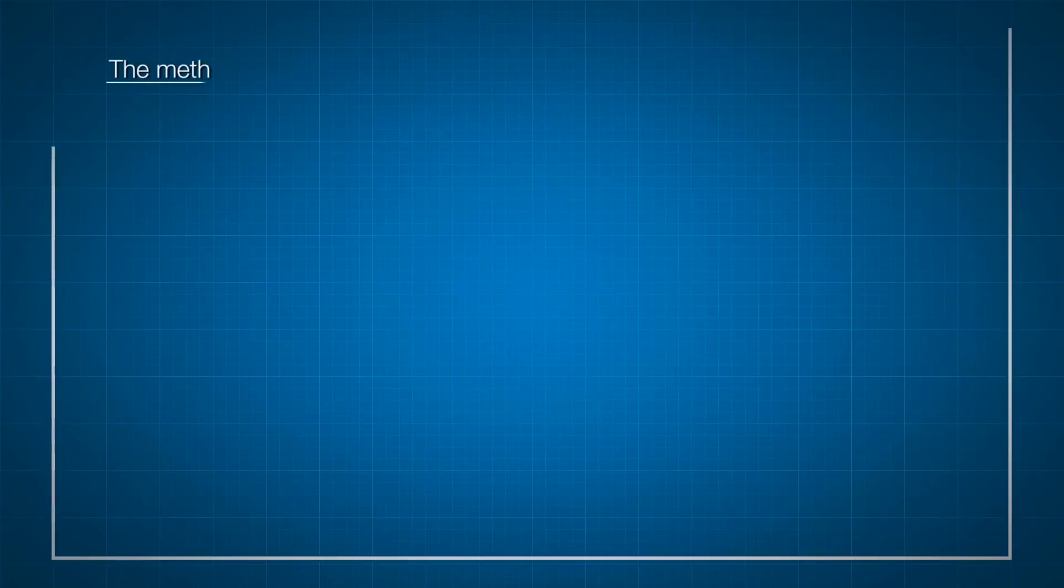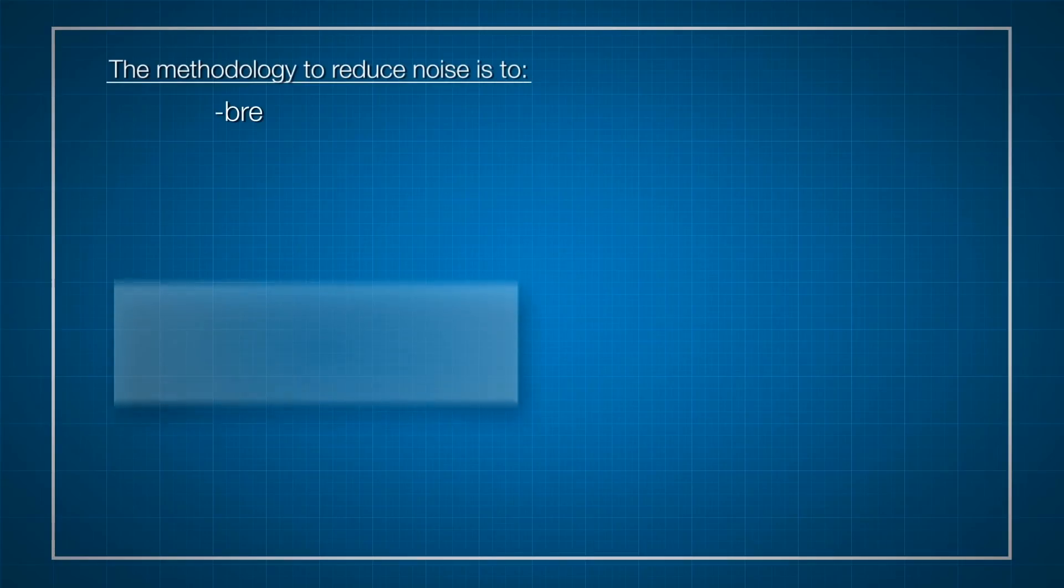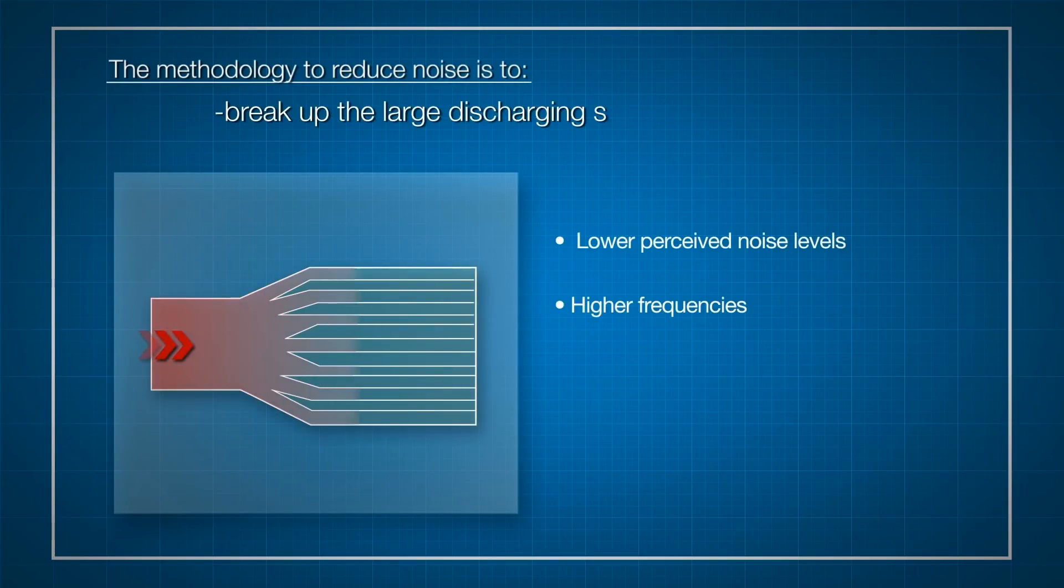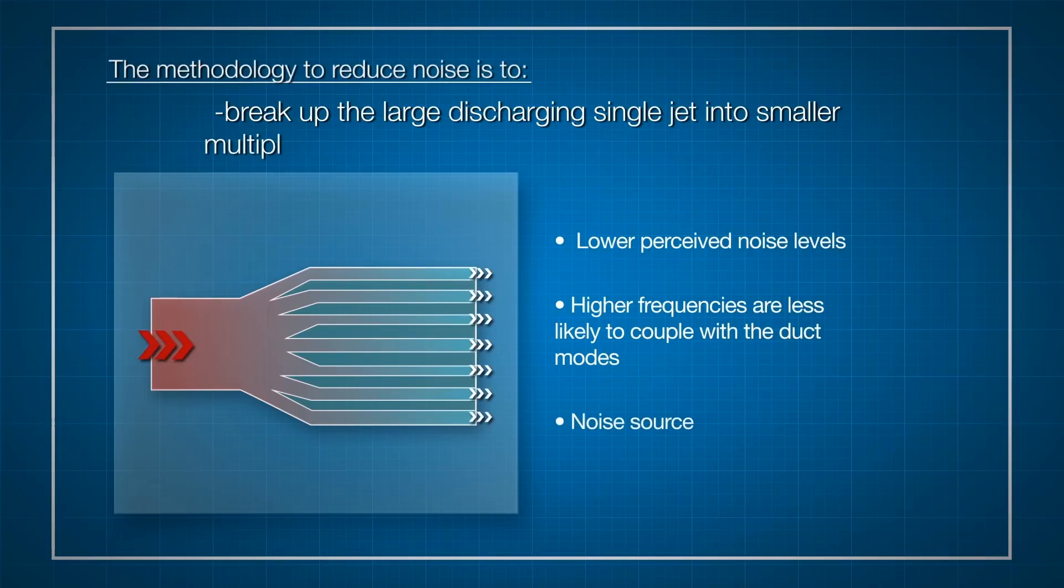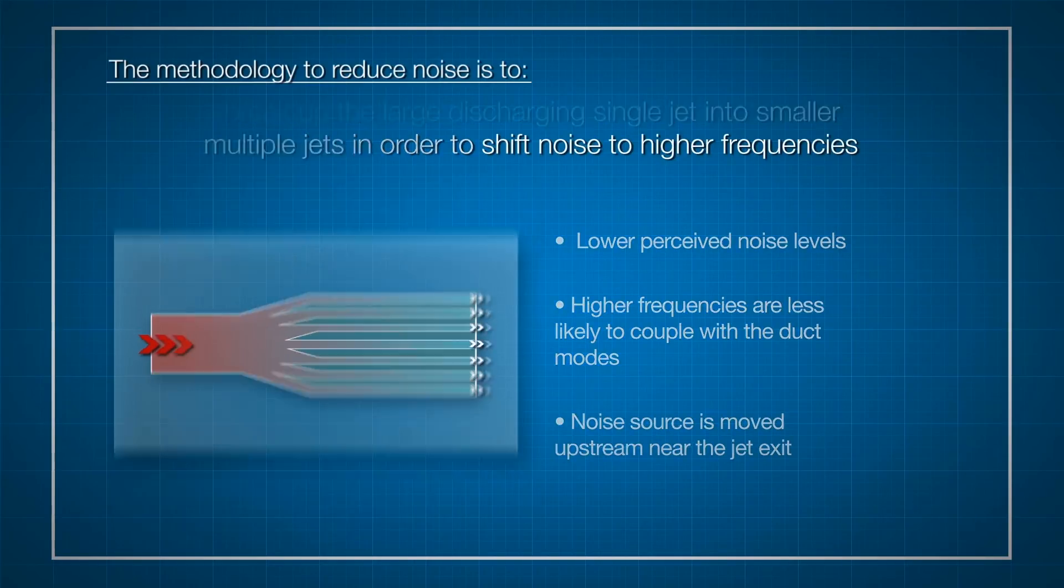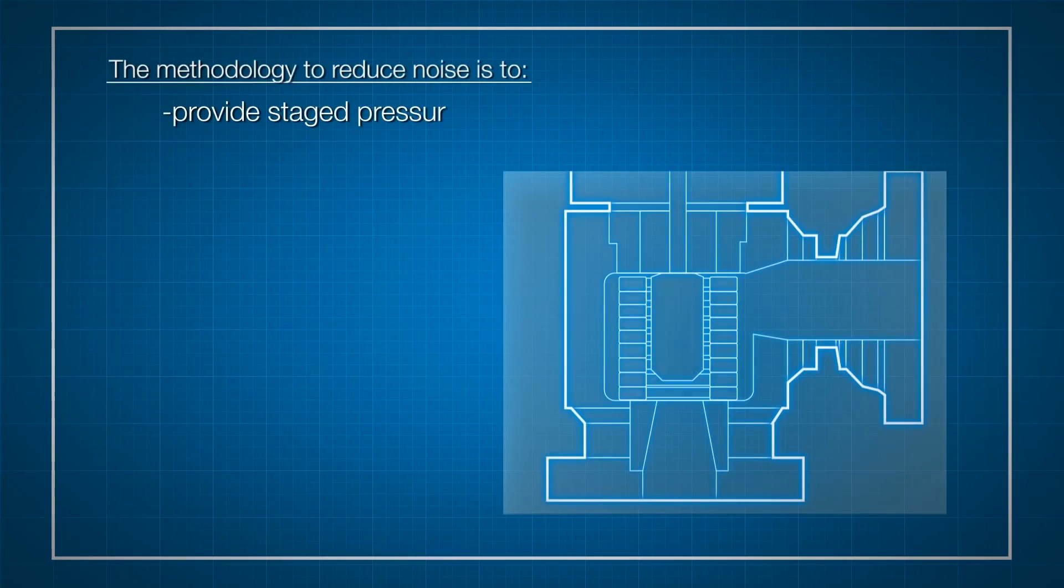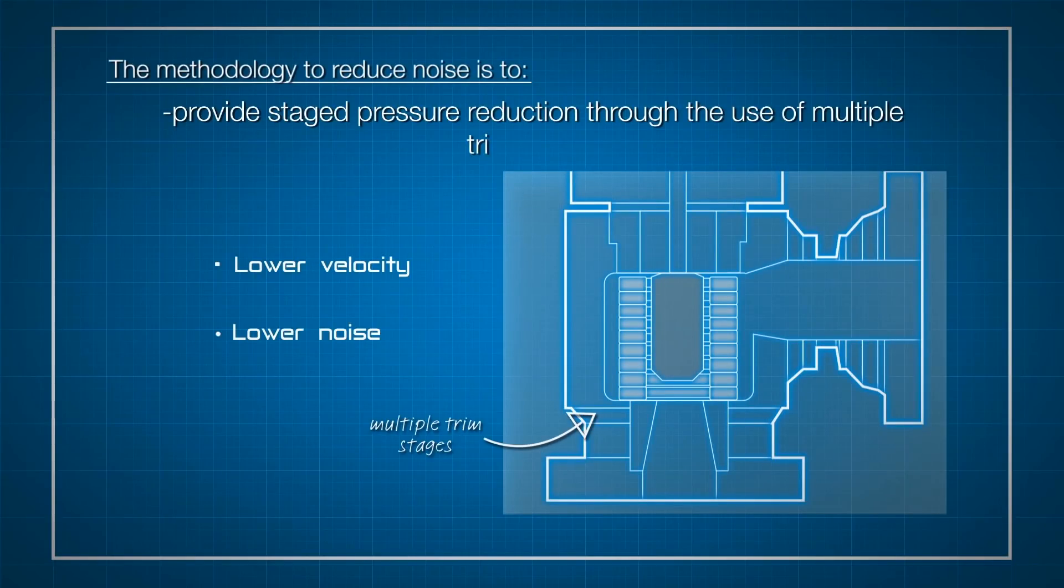The methodology to reduce noise is to break up the large discharging single jet into smaller multiple jets in order to shift noise to higher frequencies, and provide staged pressure reduction through the use of multiple trim stages.